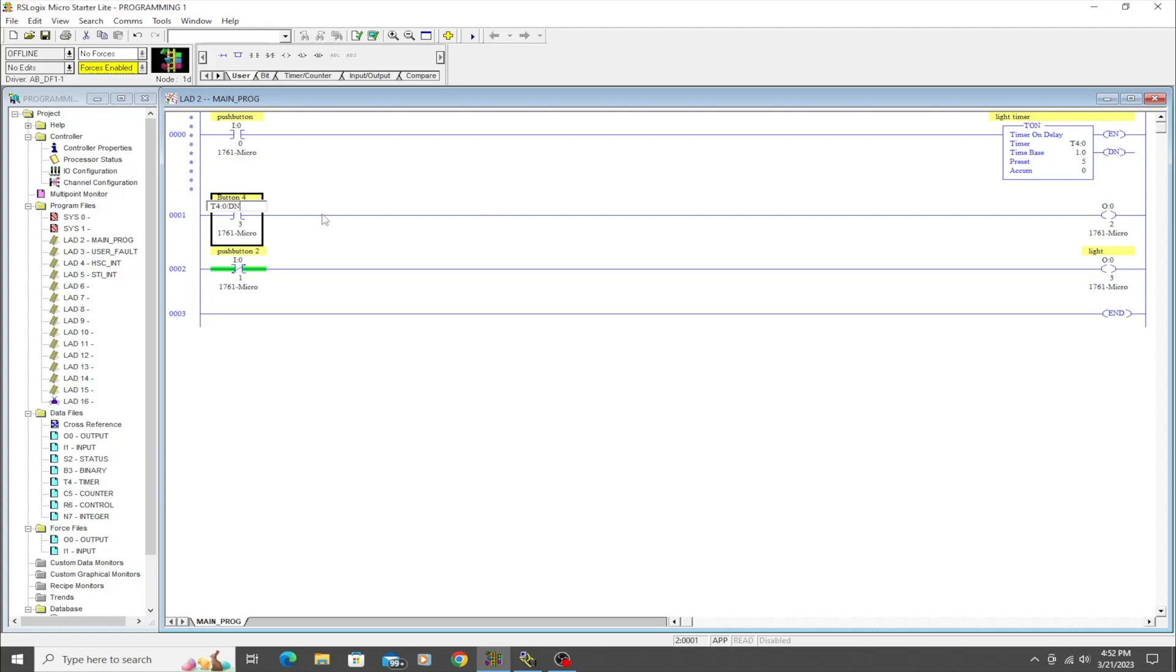So I'm going to re-address this examine-if-closed instruction and I'm going to name it T4:0. So now at this point, it's associated with this timer, but I want to tell it to do something. So I'm going to say forward slash DN, and that just means done. So when this timer times five seconds, it is then going to flag this high. This is going to turn green.